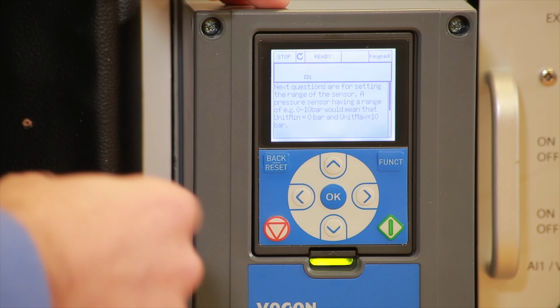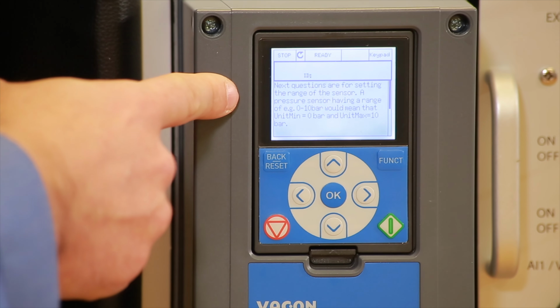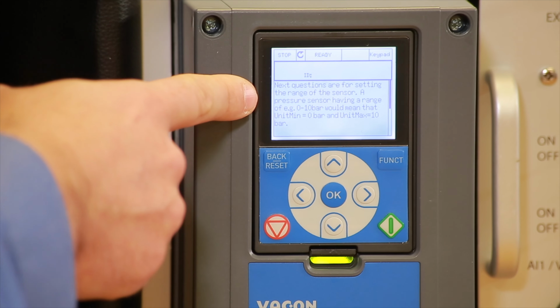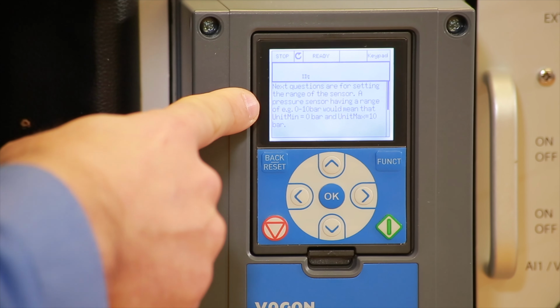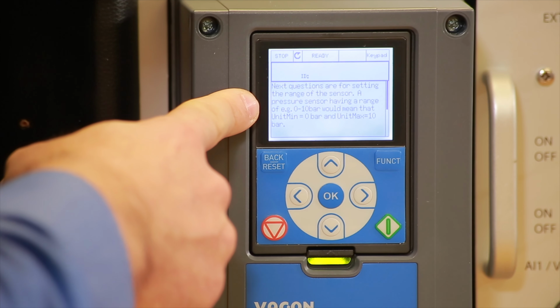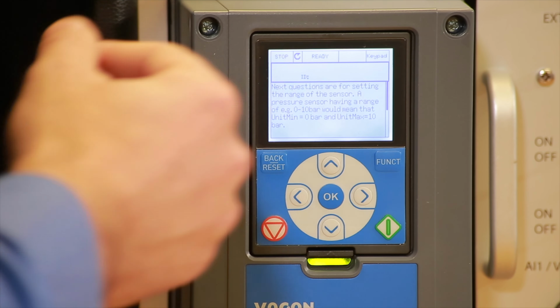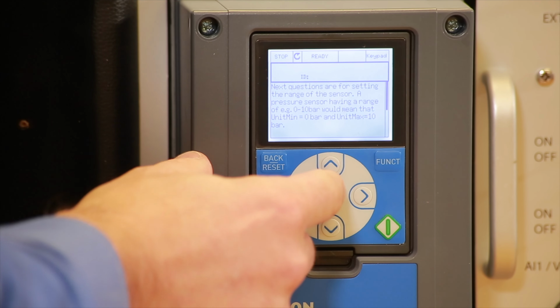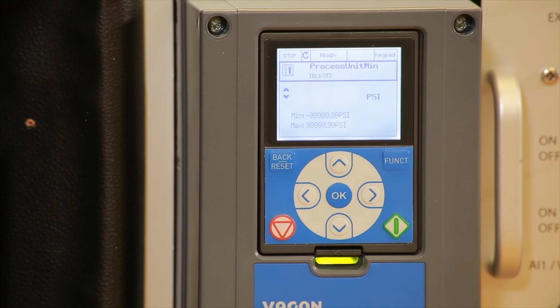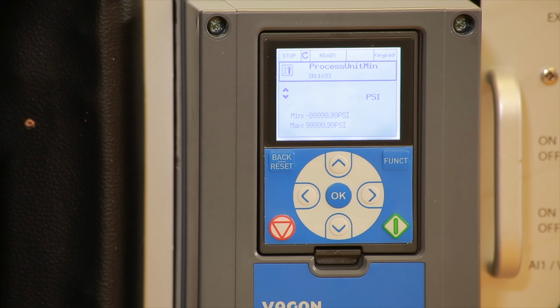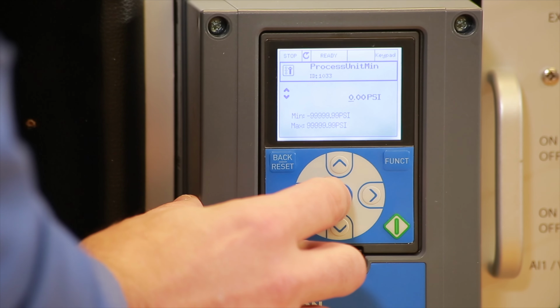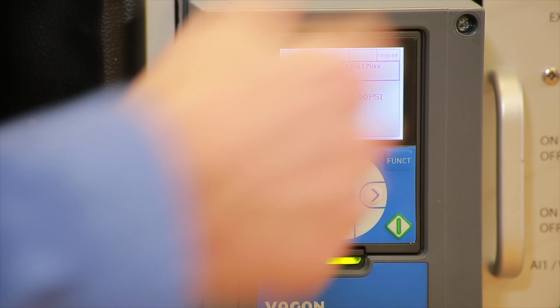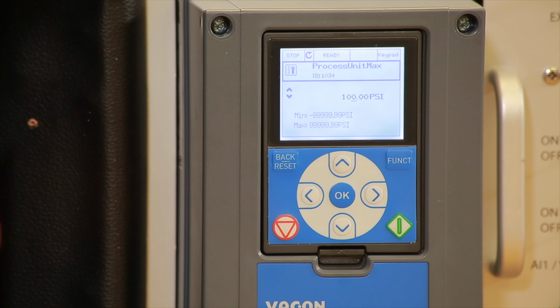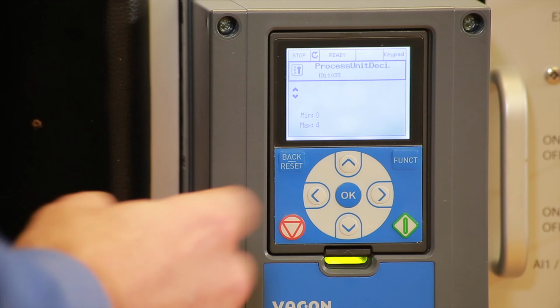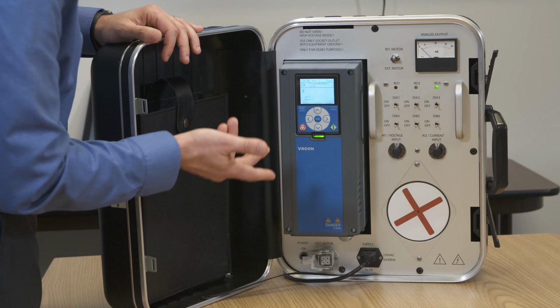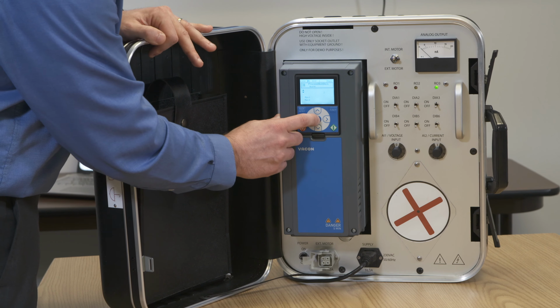All right, so once we select PSI, the drive says, the next questions are for setting the range of the sensor. A pressure sensor having a range of 0 to 10 bar would mean that minimal is 0 and maximum is 10 bars. So we're going to click OK. And now we're going to say what is the pressure transducer range that we have. We have 0 PSI as minimal, and maximum by default it's 100. You could change that to 150, 200, whatever you like. So we'll leave it at 100. And then the process units, 2 decimal places is fine, so we'll leave it at that.